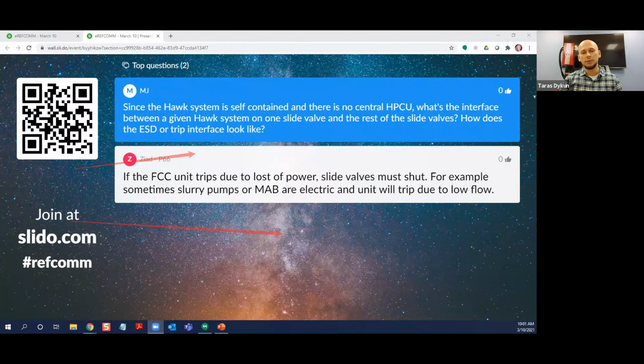How does the ESD or trip interface look? It's the same way. Basically, you have an ESD signal coming from the SIS system to the solenoid valves, which, whenever a refinery has a trip, removes the power to the solenoid valves, which trips the system. We will not be connected to the ESD solenoids. We just will be connected to see if you have an ESD trip. We don't want to interfere with any of your ESD solenoid functionality. We just notify our Hawk to make sure it doesn't run the other way because there is an ESD trip.